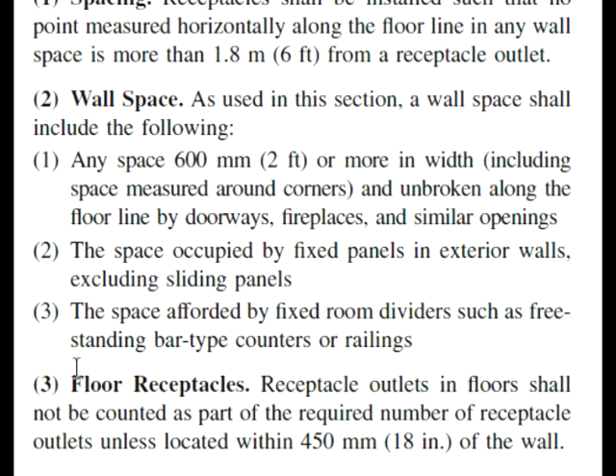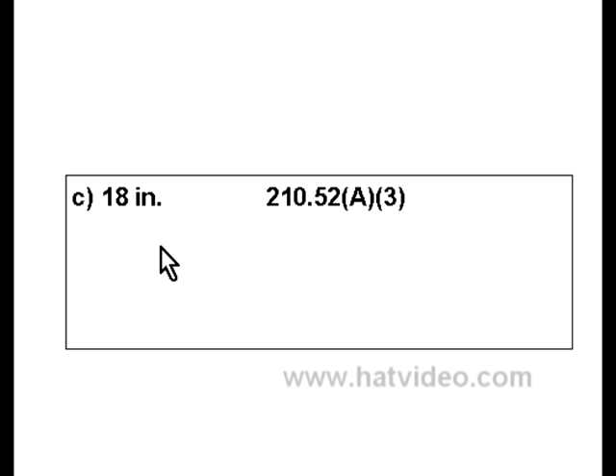Here we are at 210.52(A)(3). It says floor receptacles, and this is almost word for word: Receptacle outlets in floors shall not be counted as part of the required number of receptacle outlets unless located within 18 inches of the wall. 18 inches is choice C in the answers of our exam.